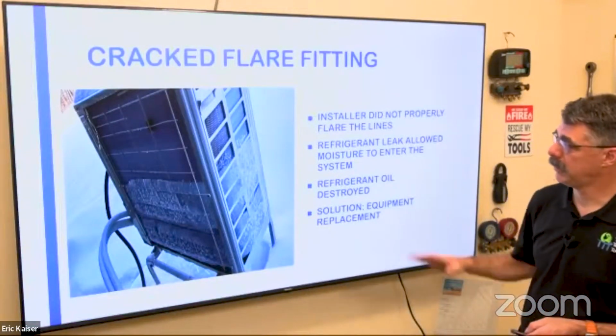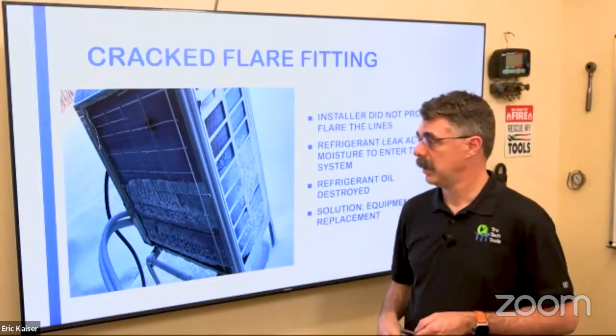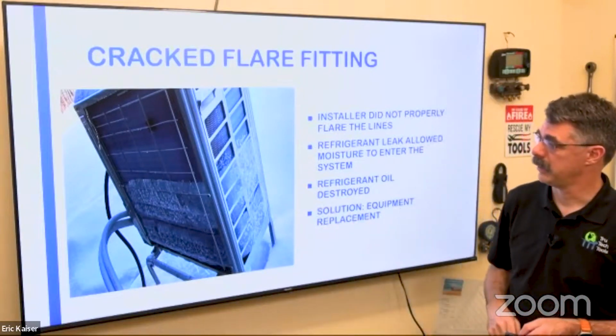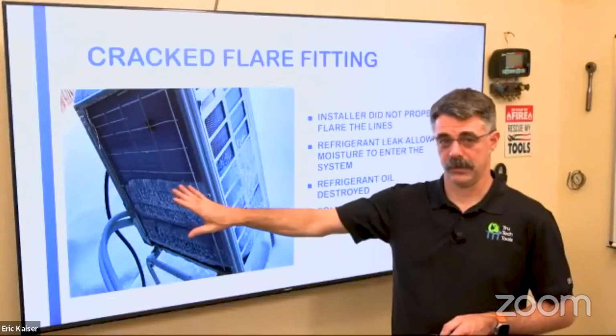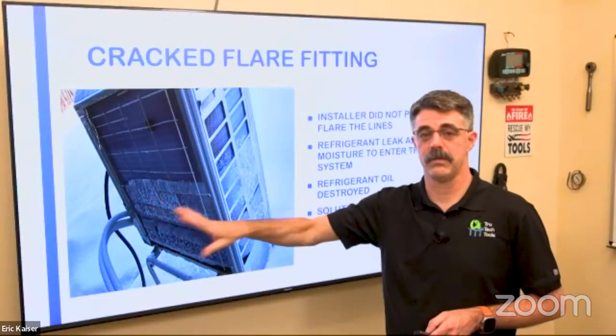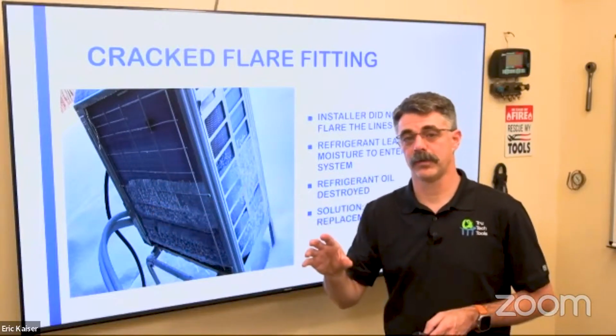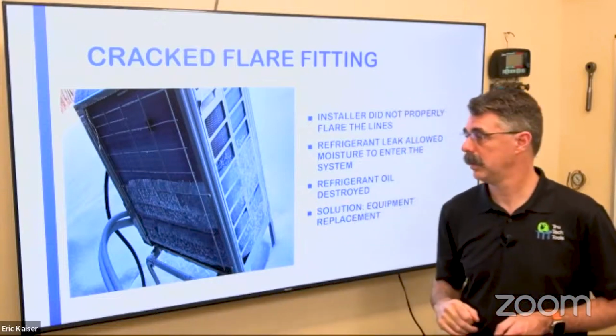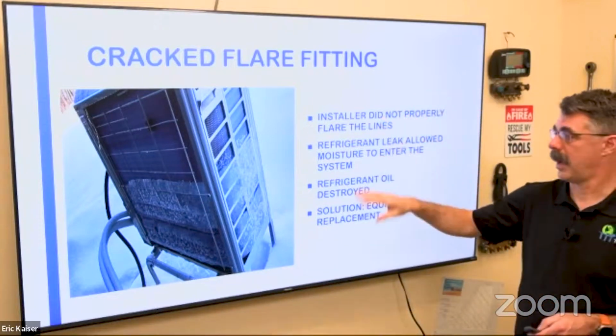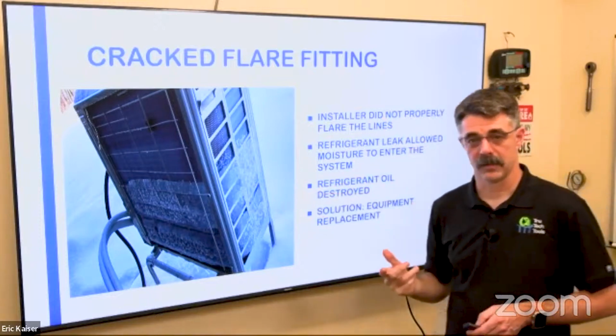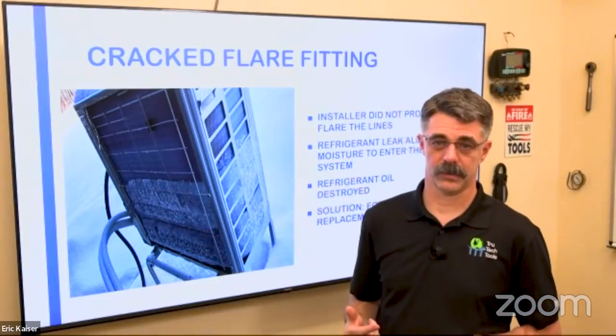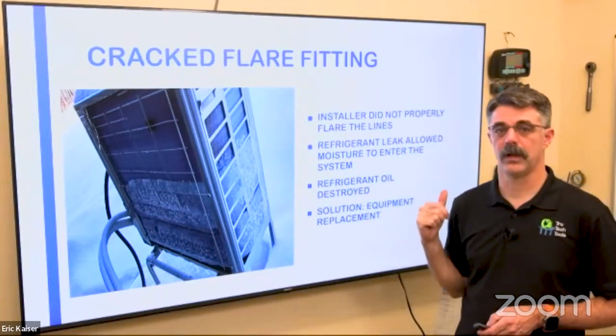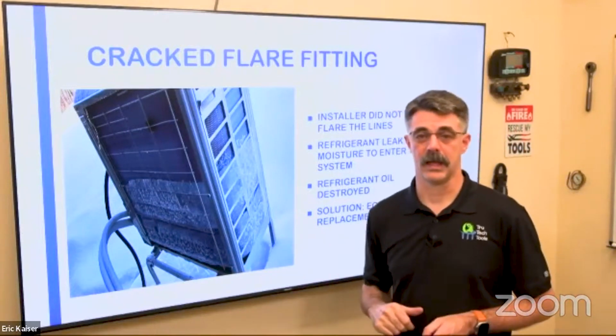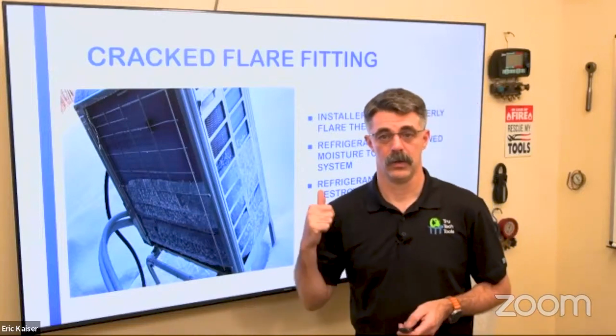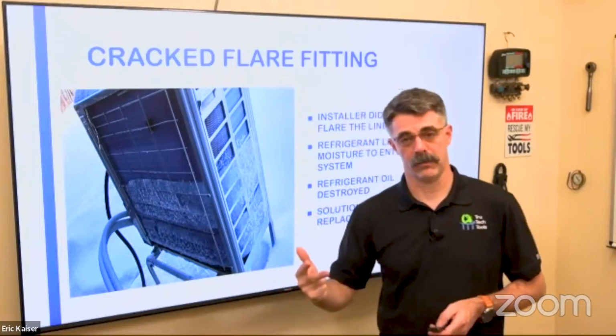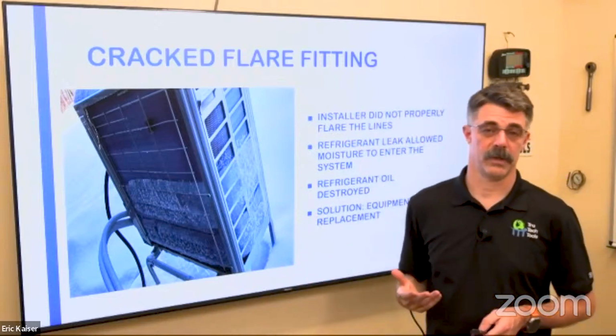All right. Now, this is the result, and this is actually Bill's house, of a cracked flare. His heat pump froze up, not frosted. This is hard ice. If you ever see hard ice on the outside coil of a heat pump, you've got a problem. It should only ever be frost that can be removed with a defrost cycle. So they didn't properly flare the lines. The leak happened in the wintertime and allowed moisture into the system, which destroyed the refrigerant oil, and the solution ended up being that he had to have a completely new system put in. New outdoor unit, new lines, new indoor coil, because all of them had contaminated oil in them. That can get expensive.